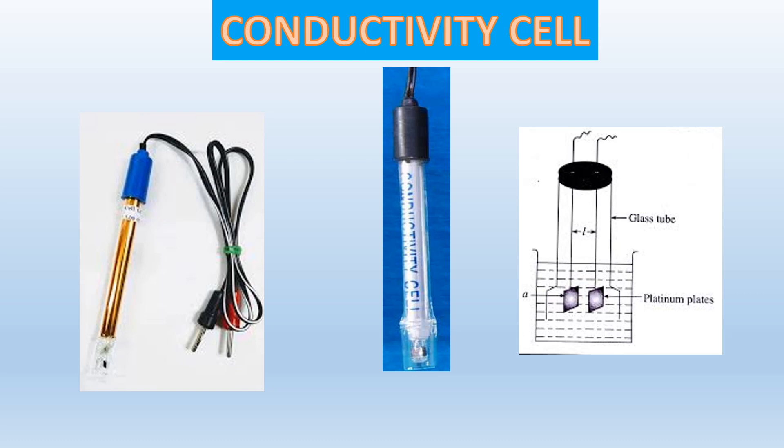As already explained in many videos about the conductivity cell, it has two platinum electrodes of half centimeter in size, one centimeter apart, so that they hold a volume of one centimeter cube of water. A schematic diagram is also shown.